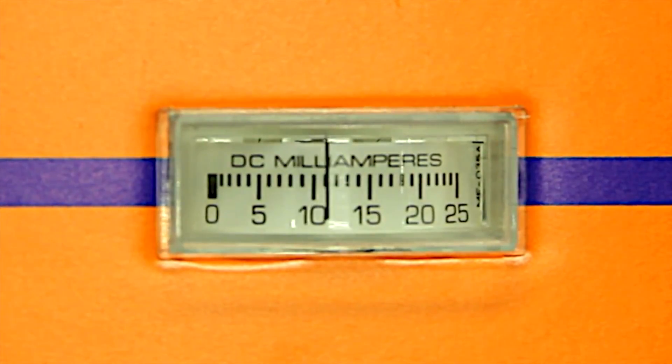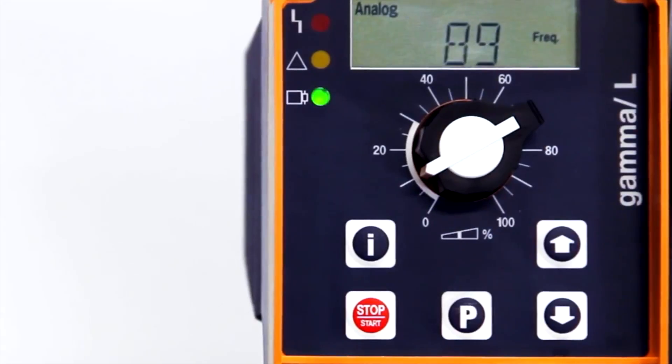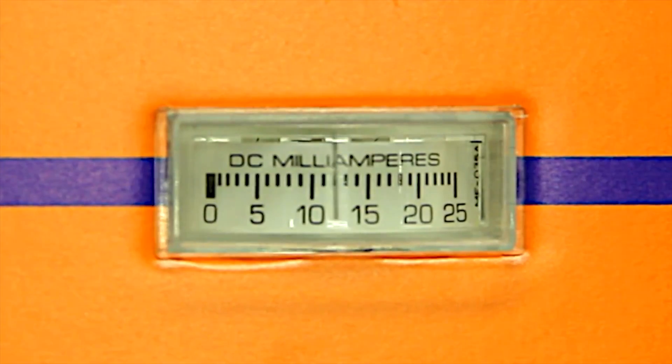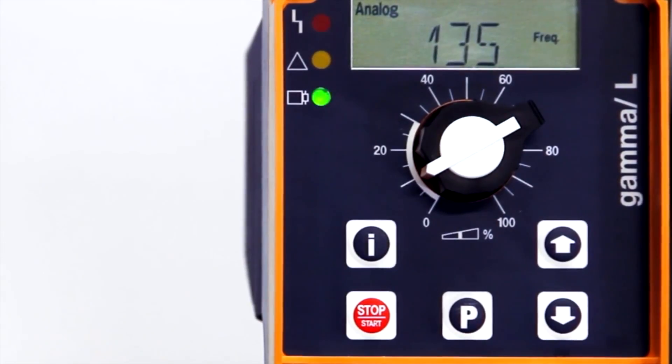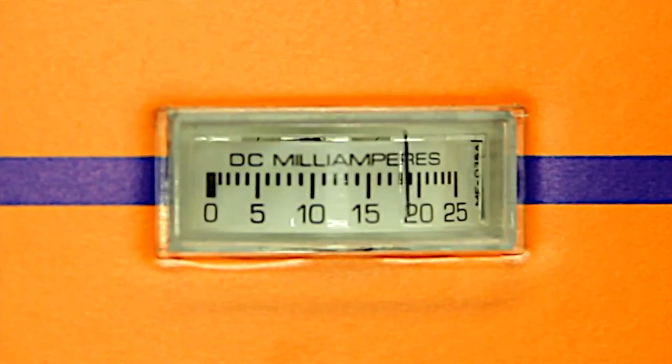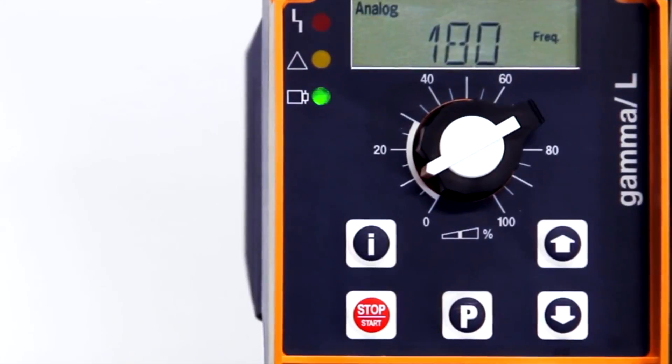We increase again to half the range, it's going to run at approximately half the speed. 16 milliamps, which is three quarters, goes up to three quarters of the range. And ultimately, at 20 milliamps, it has the pump run at its maximum speed.